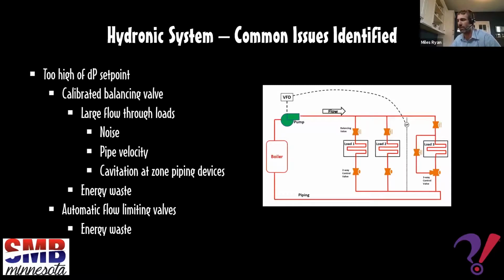I asked, what was the process you did when you came and balanced the system? And he said, I went out to all of the auto flow limiting valves, and they basically plugged their system in and verified that the differential pressure across those valves is being met. And if appropriate pressure is being met, that means that you can, I guess, trust that the valve is controlling to its selected flow rate. And he did that at all the valves, and he's like, yeah, they were all getting the flow that they required. And I'm like, yeah, but clearly they're just pinching down a ton because we have too much differential pressure in the system. Why did you end up on a 30 pounds differential pressure set point? And he's like, well, that's what they were operating when I got there, and I basically just came in and verified that they were getting the flows they need to.